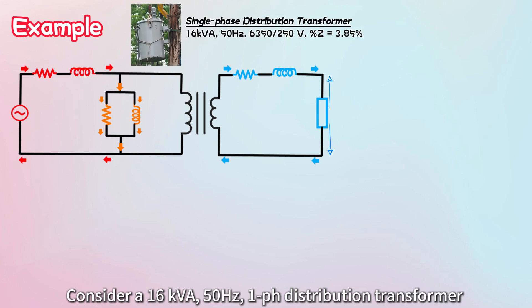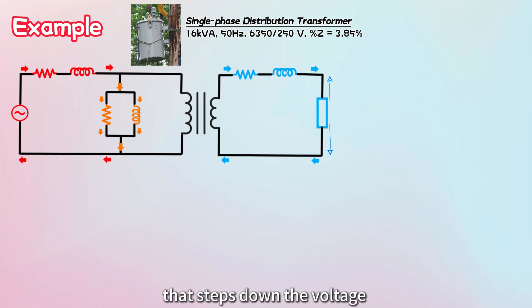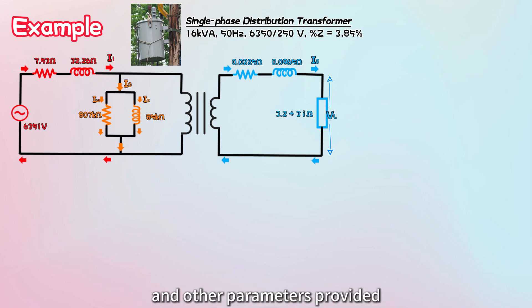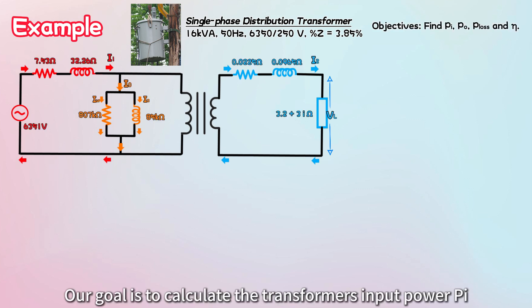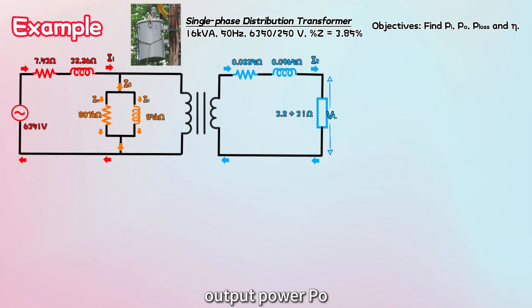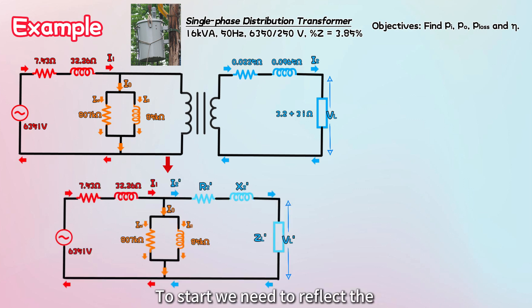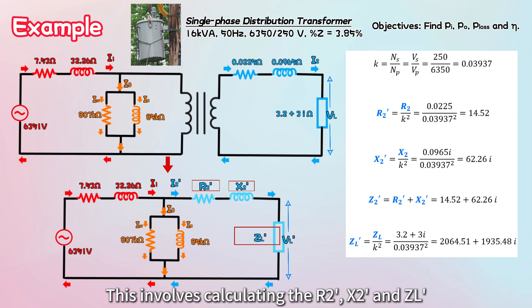Let's try a sample calculation to better understand the transformer equivalent circuit. Consider a 16 kVA, 50 Hz, single-phase distribution transformer that steps down the voltage from 6350 volts to 250 volts, with percentage impedance of 3.85% and other parameters provided. Our goal is to calculate the transformer's input power, output power, power loss, and efficiency. To start, we need to reflect the secondary circuit components to the primary circuit, calculating R2', X2', and ZL'.